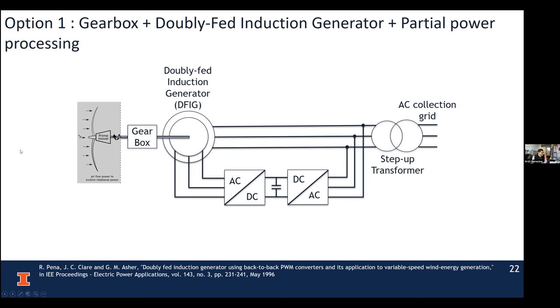So when I say 10 megawatt wind turbine, this power converter roughly can be one third of 10 megawatt to process the entire power within the operating speed range. That's a very attractive feature, and that's why this topology is the workhorse for onshore wind turbines.